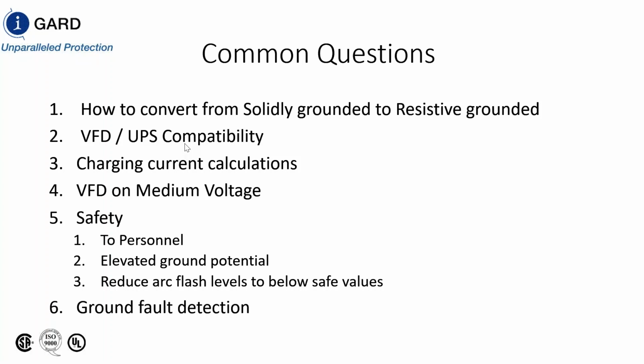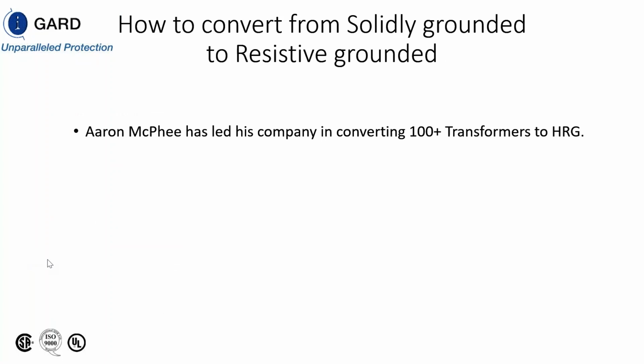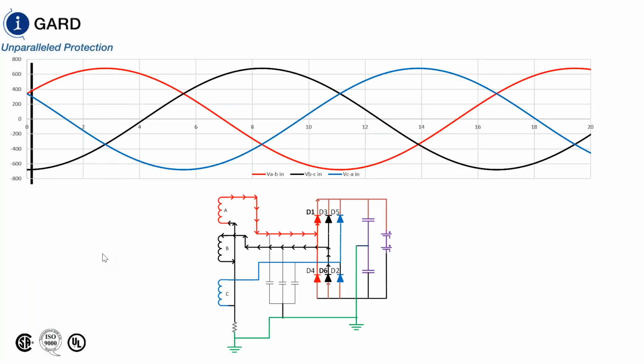There was some. Basically, all vendors will supply you the VFDs and or the UPS systems. We have many of them, as you can imagine. They will supply you a design on the front end of those units that are HRG compatible. And even if you have an existing one, you can go back to the vendor and say, look, I'm putting in an HRG. What do you have that I don't know about that's not shown on the prints on the front end side on your filtering? Do you have MOVs? Do you have anything on the front end? And everyone we've worked with has said, hey, you're good to go. We haven't had any that we turned the HRGs on and we lost something or had issues.